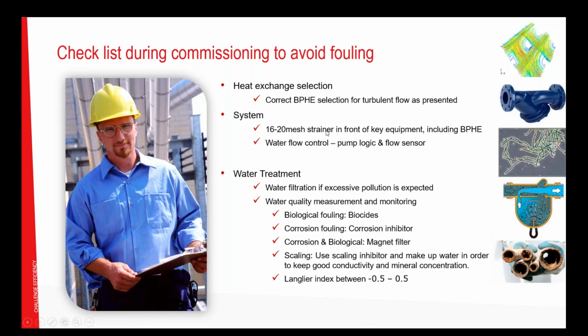With a strainer, this can be stopped before the heat exchanger, so that the heat exchanger doesn't become the strainer. And then water flow control, making sure that water is flowing, because turbulence is the key factor for avoiding fouling build-up. When it's for an open loop, the recommendations for open loop water are the same for almost all heat exchangers. There are many good open loop installations, but of course there are some bad ones as well.